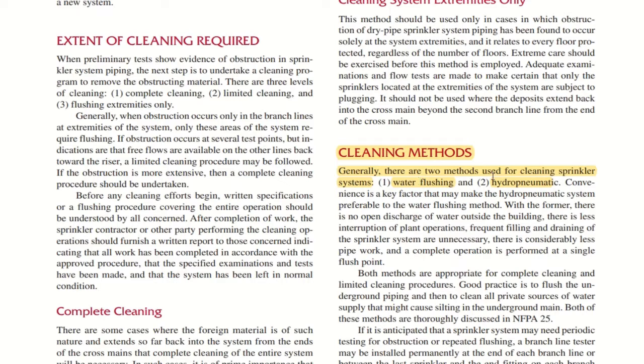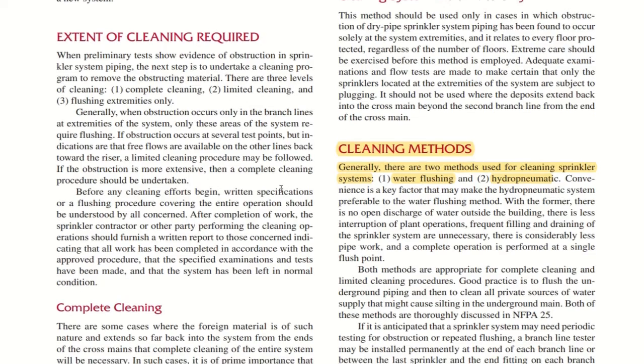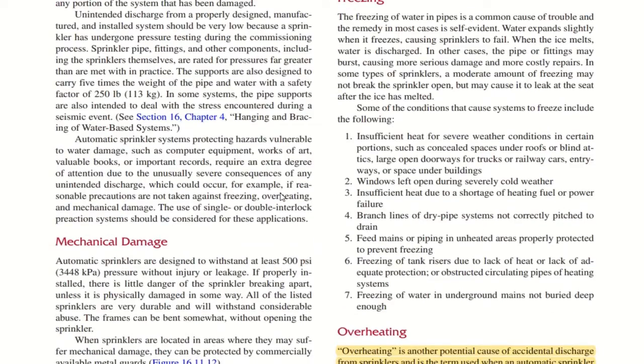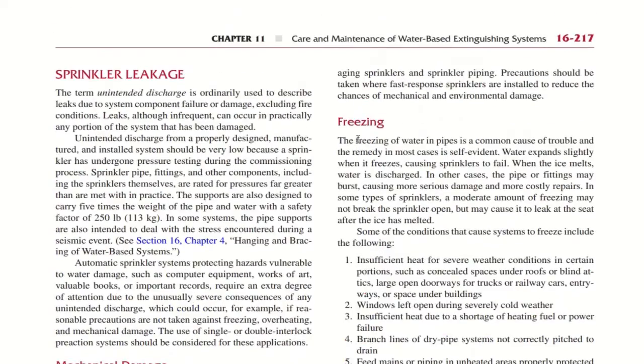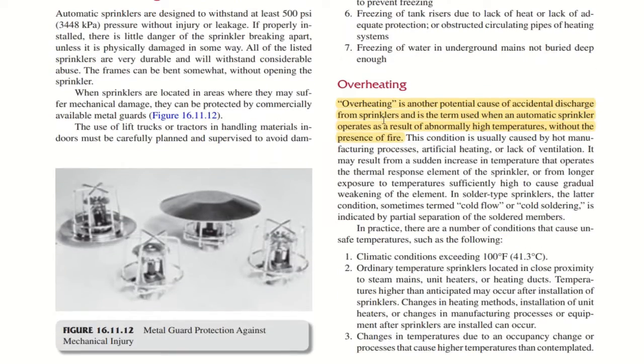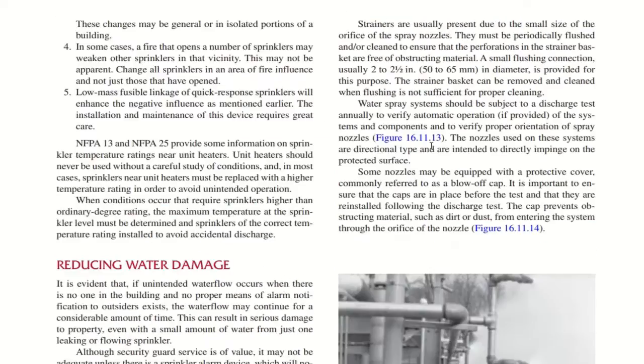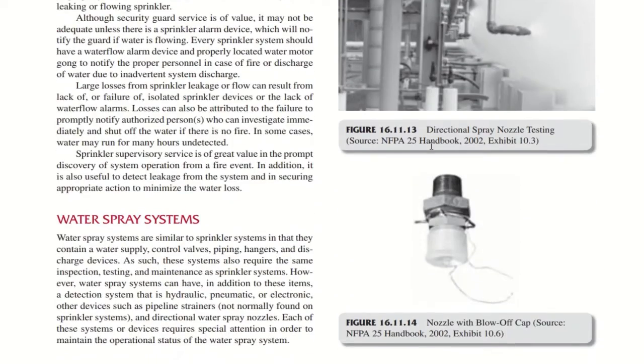So generally there are two methods used for cleaning sprinkler systems. One is water flushing and the other is hydro pneumatic. So sprinkler leakage, mechanical damage, freezing, overheating. Overheating is also another potential cause of accidental discharge from sprinklers, and is the term used when an automatic sprinkler operates as a result of abnormally high temperatures without the presence of fire. This is an important point which I highlighted.